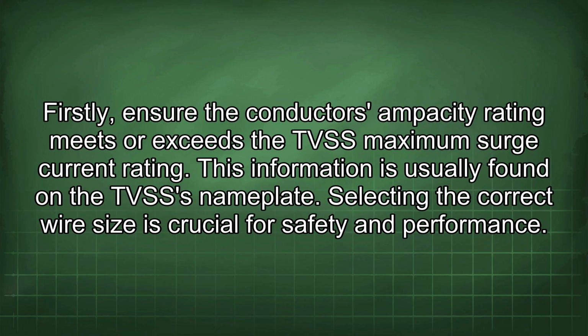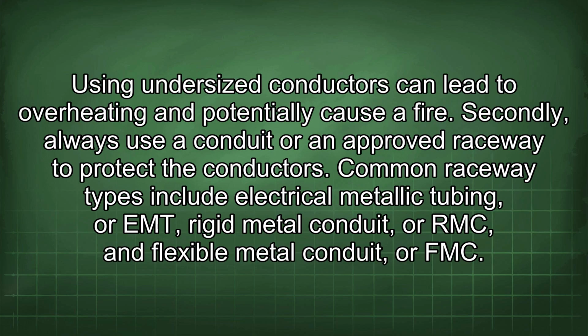Firstly, ensure the conductor's ampacity rating meets or exceeds the TVSS maximum surge current rating. This information is usually found on the TVSS's nameplate. Selecting the correct wire size is crucial for safety and performance. Using undersized conductors can lead to overheating and potentially cause a fire.